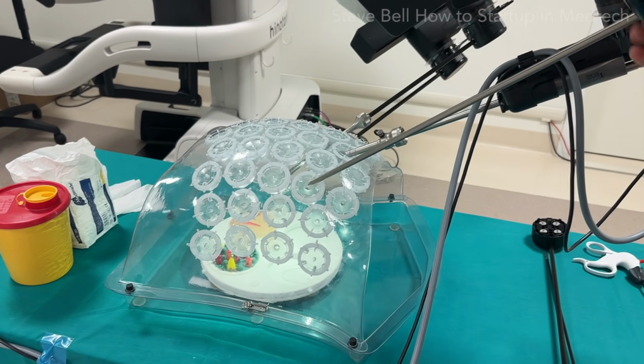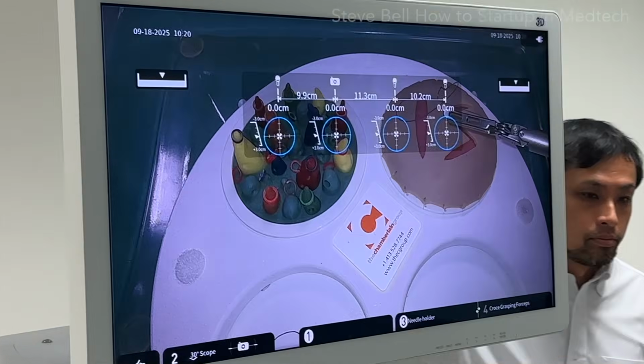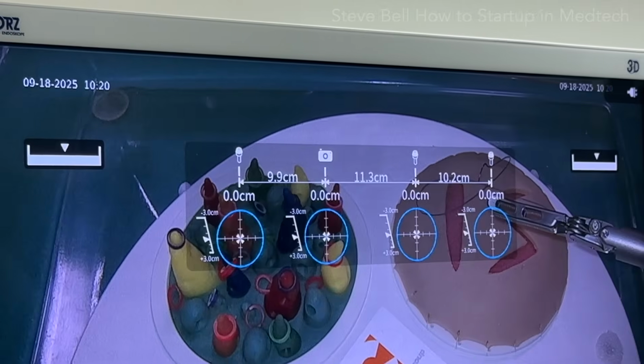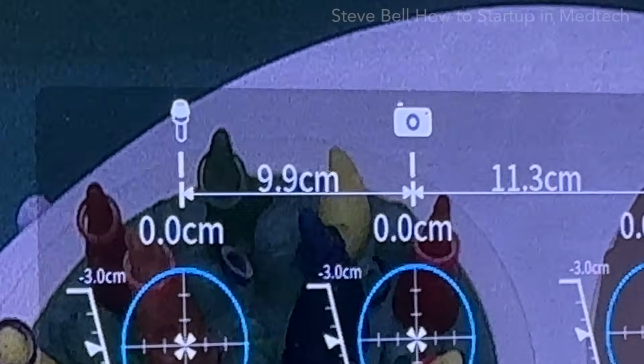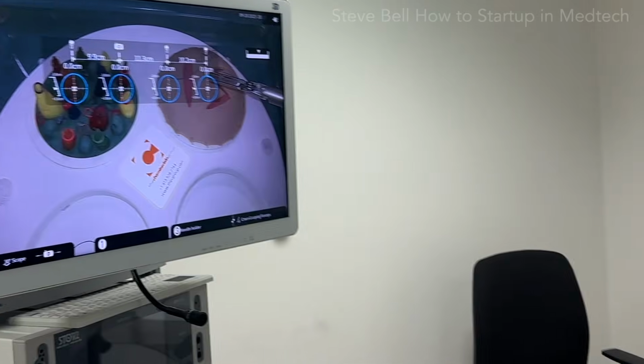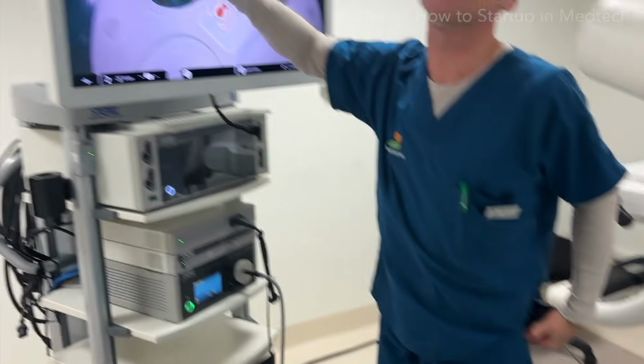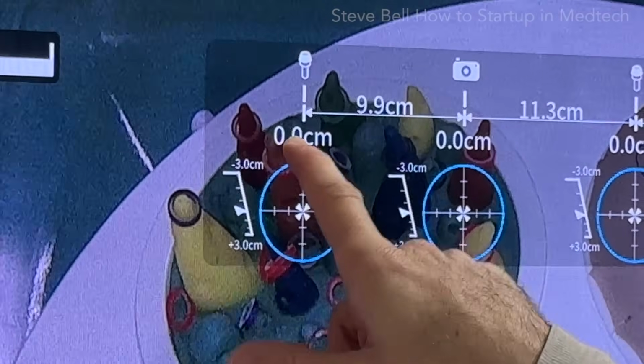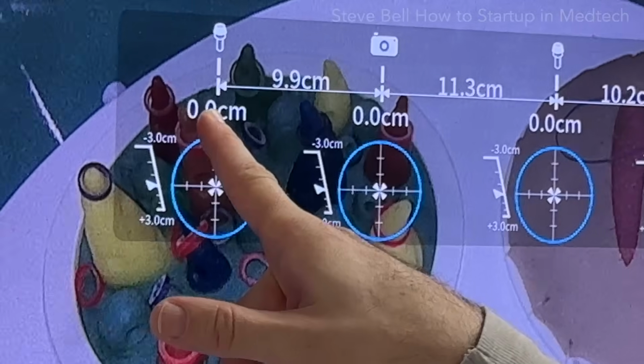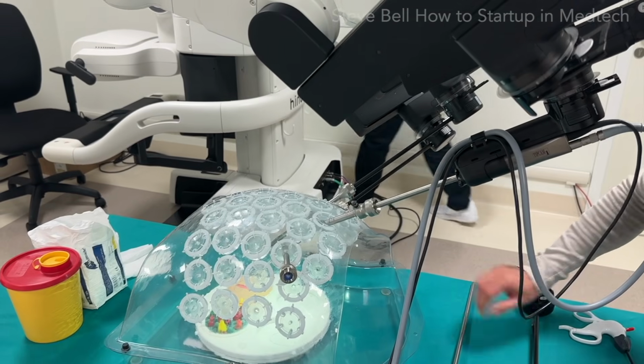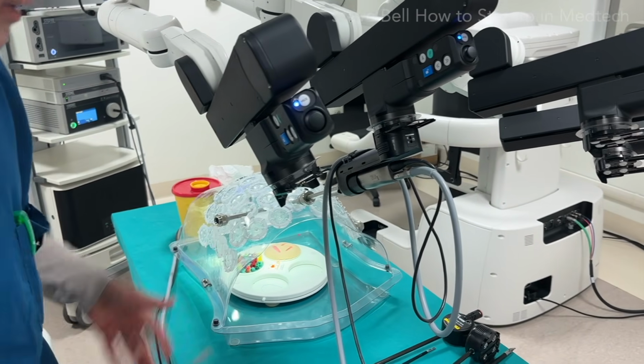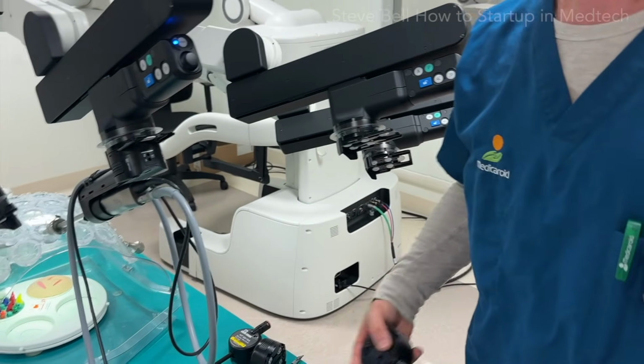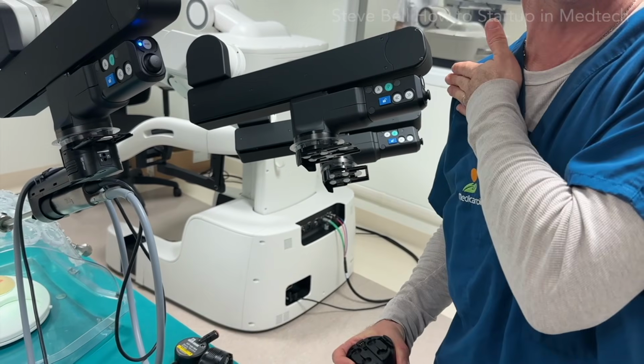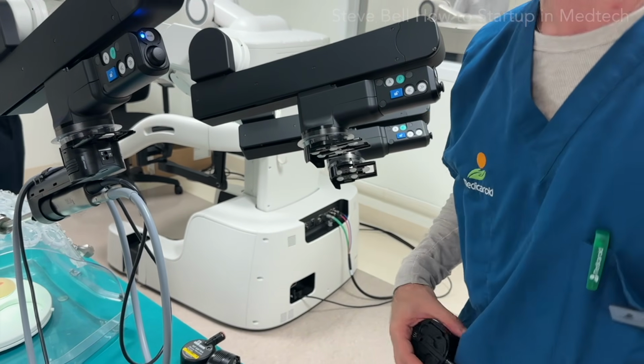So as I promised you, just look here. Here's a measurement of 9.9. This is absolutely recommendable because it's within our recommended distance. So you see here, because the dome is so thin, it's 0 centimeter. But normally you would have here 8 or 6 centimeters or 4 centimeters, depending on the body mass index alterations. Yeah. So this is the pivot point measurement. Yeah. Good. So this one is there, and it's all your preference. You can now attach your instrument and put it into space, but I like to do my pivot setting first. Then I have done this topic, and then I attach the instrument.